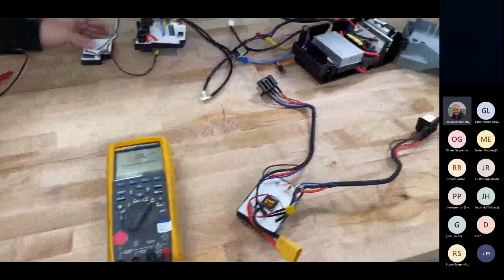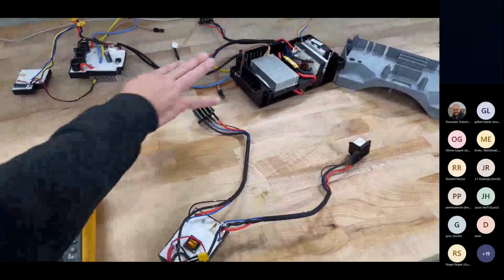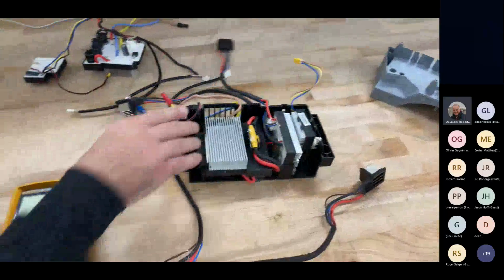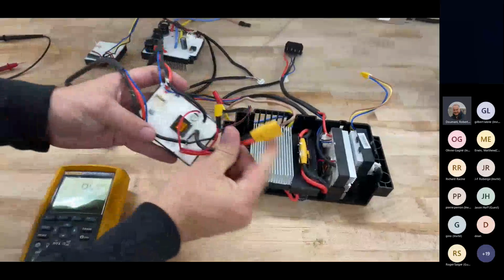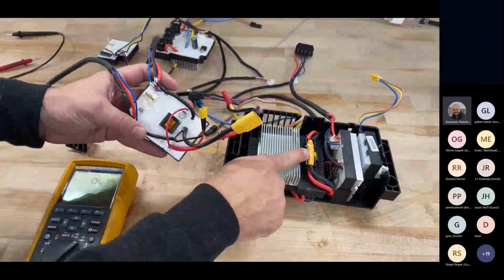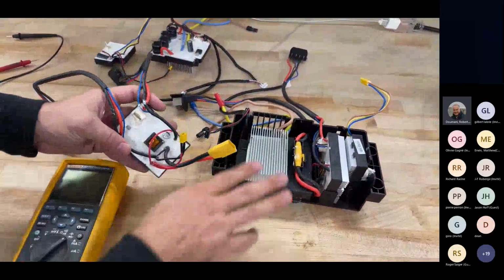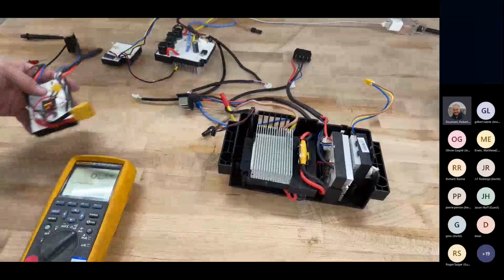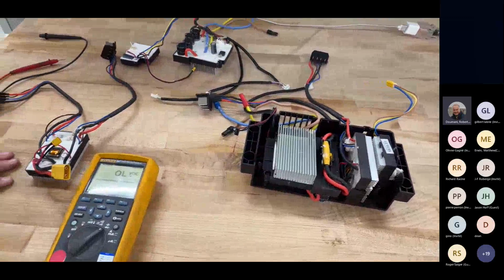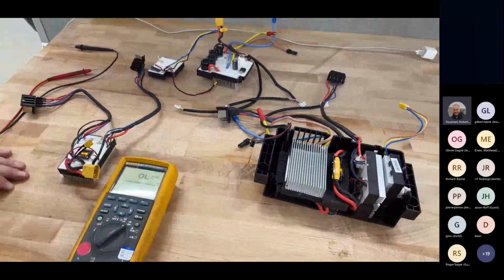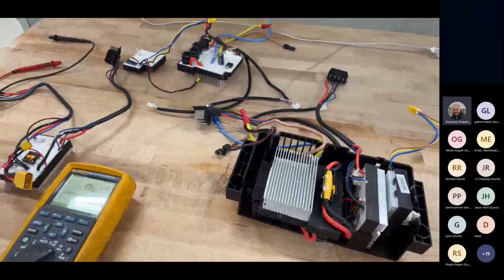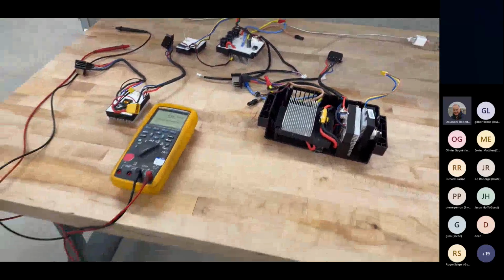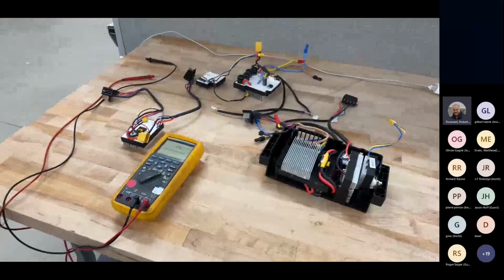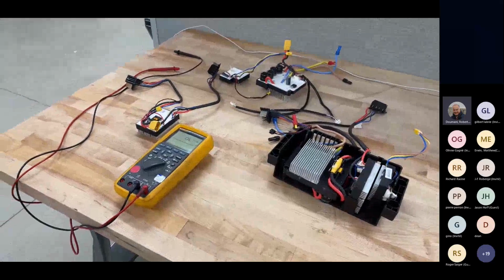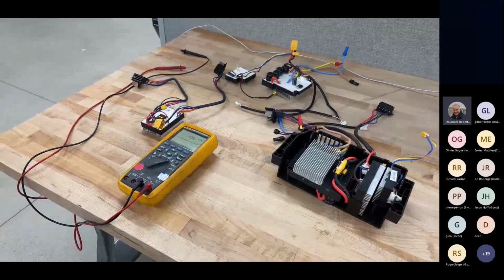With this box, you cannot release the input signals without opening the box up, so you do have to remove them from the box to test them. The only thing you can test once you remove this, as shown in the video, once the PCBA box is removed, you can still test continuity for the motors while those wires remain on the machine.